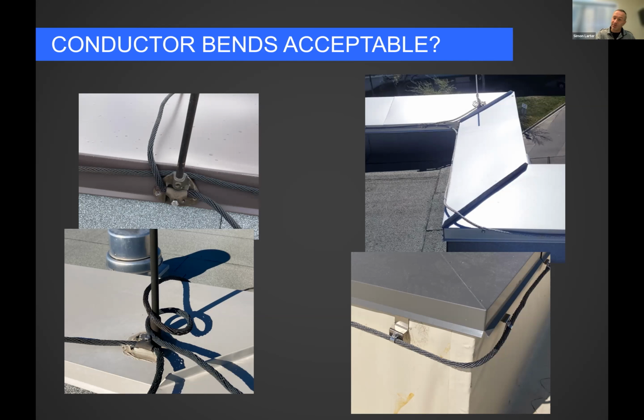But anyway, on the right-hand side, now you see some acceptable conductor bends. One thing that will happen with somebody who's not fully trained in the lightning protection code is they'll make a real tight bend at the corner. They'll just jam it right in there because they want it to be as neat and clean as possible. That's just not how we can do it.